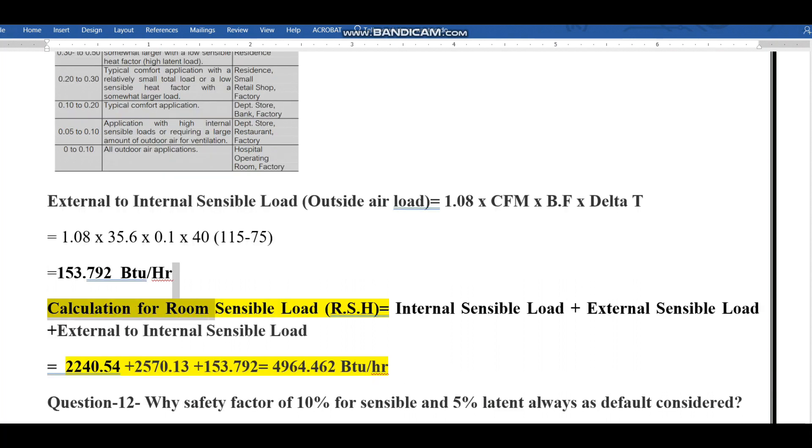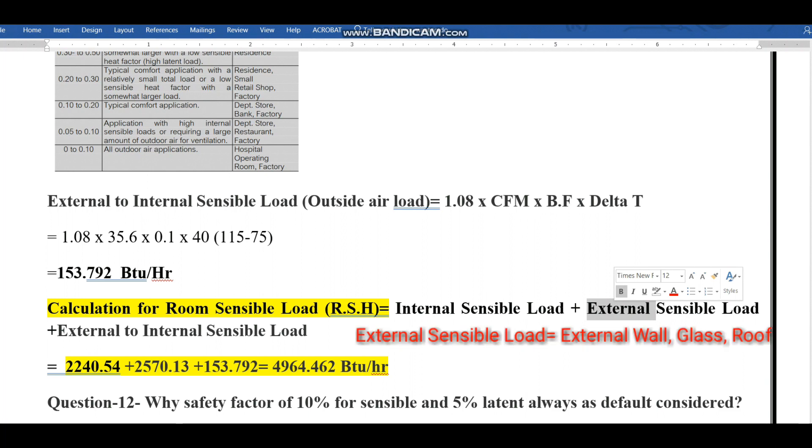Now we can find the answer for total room sensible load: room internal sensible load, room external sensible load, and external to internal sensible load. Room internal sensible load includes people, lighting, power or motor load, equipment appliance load, floor and partition. External sensible load includes roof, wall, glasses. External to internal sensible load is ventilation, the makeup air.